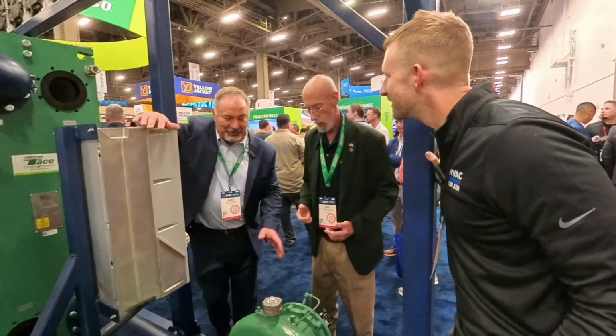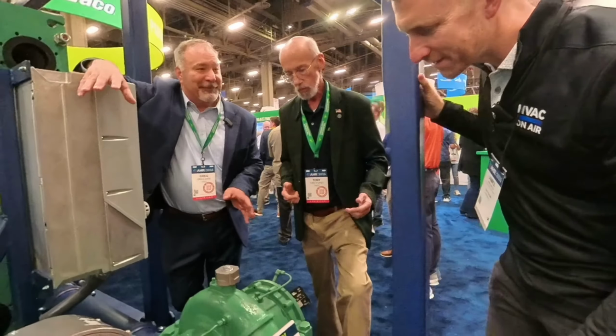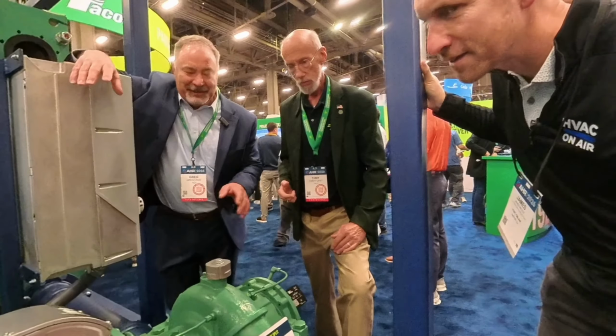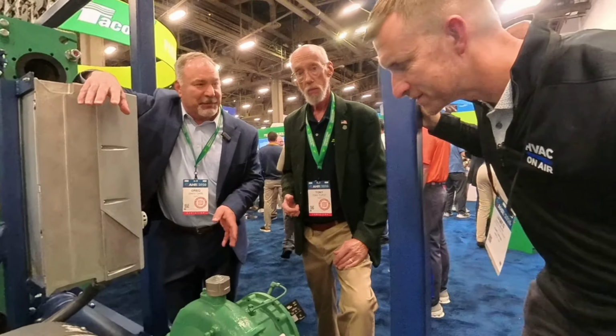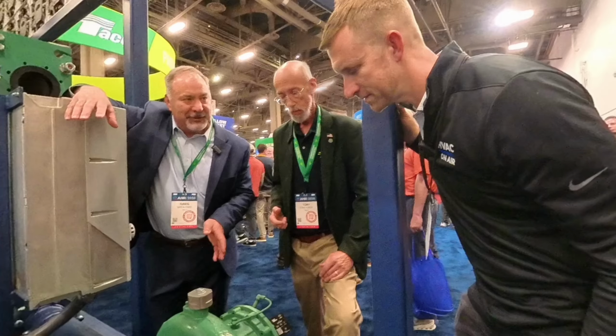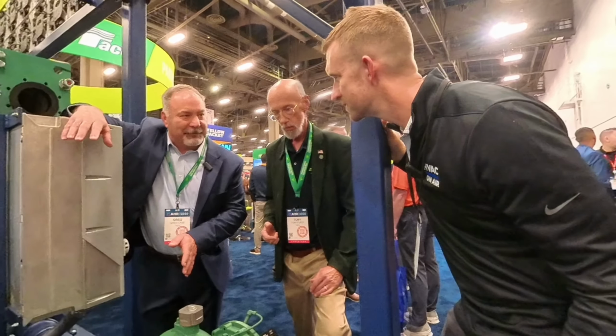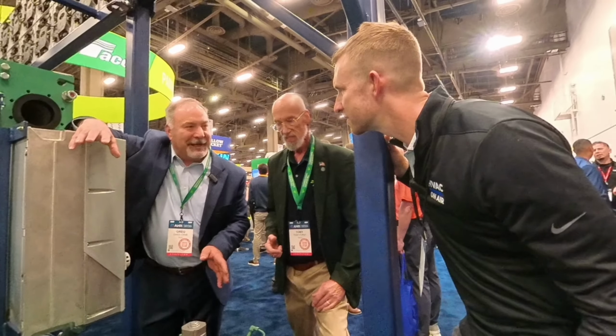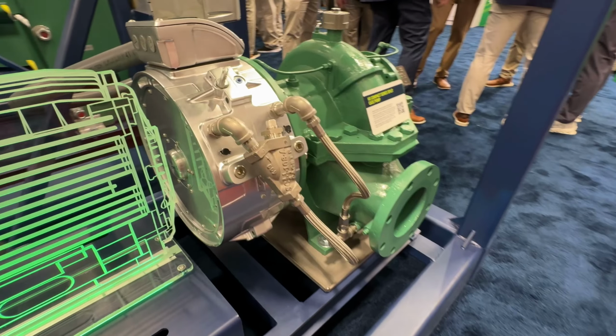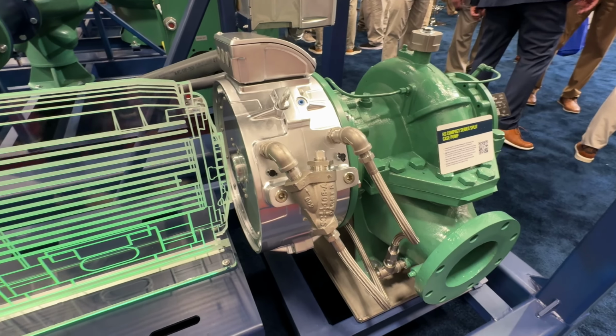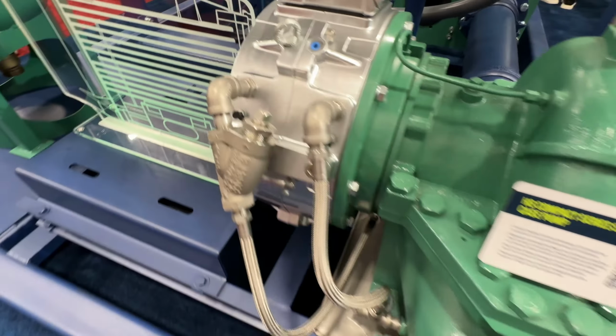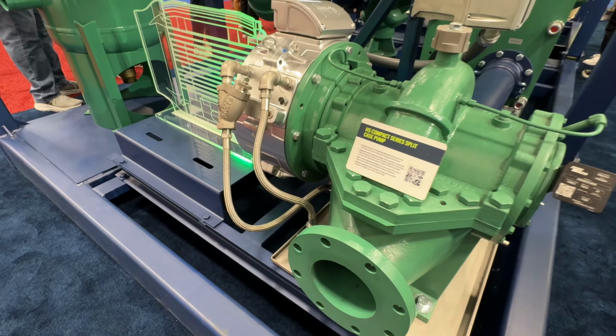All right, so this is our brand new offering, just launching it here at ASHRAE. This is a horizontal split case pump. It is close coupled to an axial flux motor. So what that means for us is this axial flux motor is about, the motor itself would be about 1/6 of the weight of a normal motor.